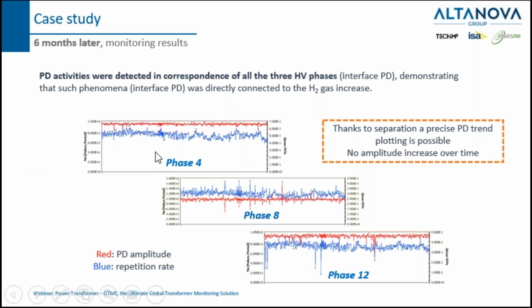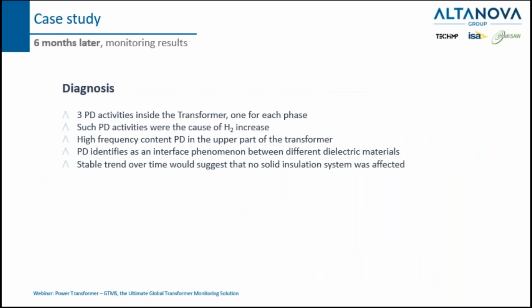Again, this is the trends only related to the most dangerous PD in the transformer, in this case, the interface PD. So PD in this case were detected for all the three phases, demonstrating that this kind of PD was directly connected to the increase of the H2 value. So after this additional 6 months of monitoring results, the diagnosis was the following. So 3 different PD activities inside the transformer, one for each phase. Such PD activities were the cause of the increase of the H2.